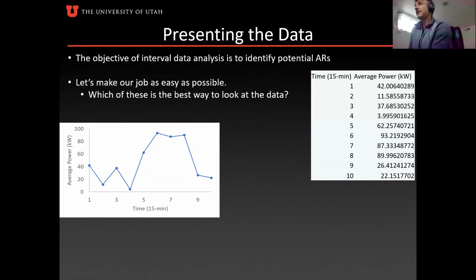Yeah, exactly. So if you have this 15-minute average data and you're connecting the points, you're implying that what's happening between there is actually happening. Like Blake said, the data points show you this pattern: a higher peak in the 5 or the 6 to 8 range, and a lull outside of that. But when you connect the points, you're saying the average power draw at 4.5 is 40 or something like that. And that's just not what the data shows at all.